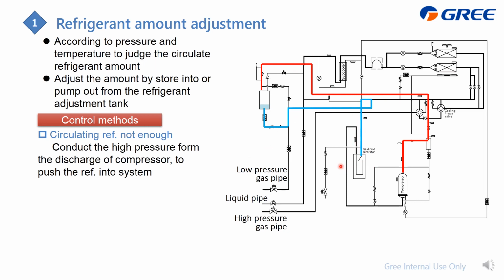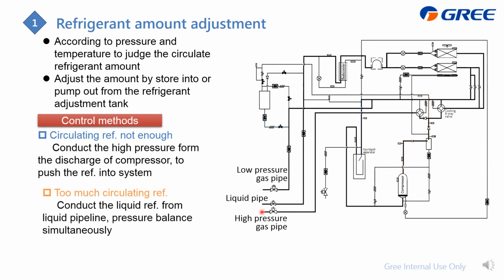Just pump it into the gas liquid separator to join the circulated refrigerant. And if we detect there is too much refrigerant, we can also absorb the refrigerant to make it liquid, and the efficiency is the best. It will connect the piping to the liquid pipe, just like this, and also absorb the refrigerant into the refrigerant tank. It's okay. And for this one, we can adjust the refrigerant amount for the circulated refrigerant.